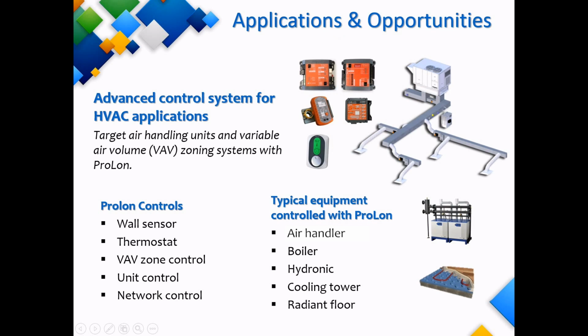What applications or type of equipment can Prolon's devices control? Let's start with the zoning systems. Prolon has dedicated controllers for rooftop units and VAV zones. Whether the system is true VAV or VVT, Prolon's devices are able to control both. We have developed controllers for other types of equipment typically found in light commercial buildings, such as controllers for boilers, heat pumps, cooling towers, makeup air units, and so on. Now in the following slides, we're going to take a look at each one individually.